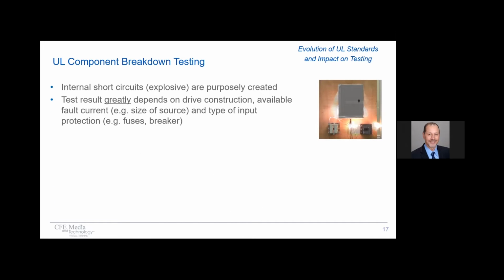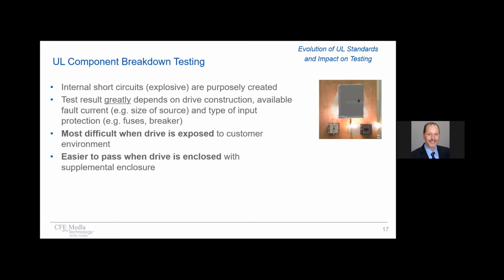During this destructive testing, internal short circuits, which are explosive and damaging, are purposely created. And the test result greatly depends on the type of drive construction, the available fault current that we talked about before, and the type of input protective device used. And it's most difficult to pass this test when the drive is exposed to the customer environment, like a standalone application. Easier to pass when the drive is enclosed within a supplemental enclosure.